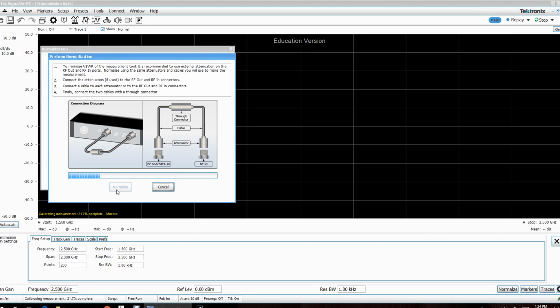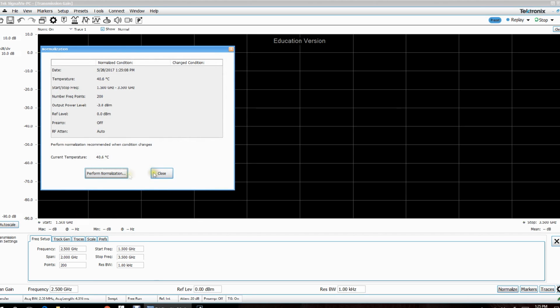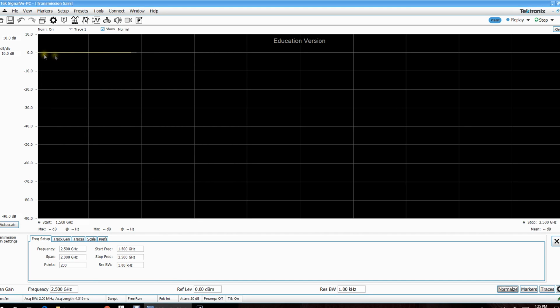Now during the normalization, it will apply a signal through the RF port and then look at it through the RF in port, get rid of the losses of the cables in between, and make sure that you have a very flat frequency response, adjust your reference, and make everything ready for you to be able to do the measurement that you want to perform. Now it's almost finished, and there we go, and we're done with that. So now we can see a very nice flat line from 1.5 gigahertz to 3.5 gigahertz, 200 points, 1 kilohertz resolution bandwidth. So it looks good.